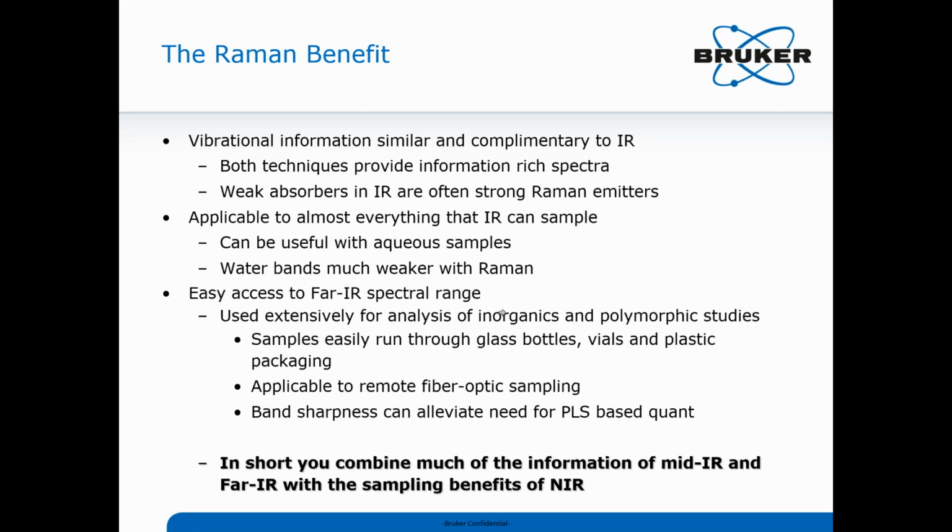And Raman is applicable to almost everything that the IR can sample. And it works really well in water samples, right? Because water doesn't have a signal, or very weak anyway in the Raman. And then it works well in the far infrared.